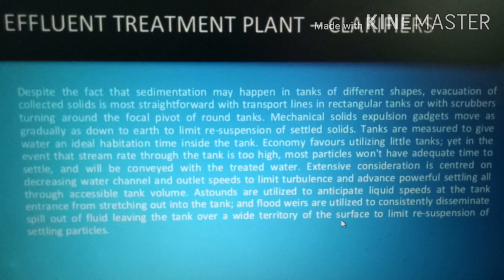Considerable attention is focused on reducing water inlet and outlet speeds to limit turbulence and promote effective settling throughout the available tank volume. Baffles are used to prevent liquid speeds at the tank entrance from extending into the tank, and overflow weirs are used to evenly distribute spill-out liquid leaving the tank over a wide area of the surface to limit resuspension of settling particles.